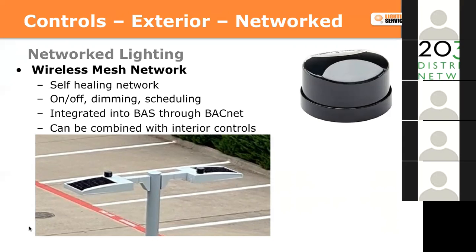We're currently installing this type of system. That picture is from Collin College down in Texas, where we've recently installed a bunch of these new LED fixtures with this system and are in the commissioning process as we speak. You can adjust light levels, turn fixtures on or off from one location or from an app. Failure reporting is one thing I didn't mention: you can see which fixtures are out. Most of the time maintenance crews aren't walking around at night trying to figure out which lights are out, so this sends an alert to the system saying a fixture at a given address is out, and it can be addressed very quickly.